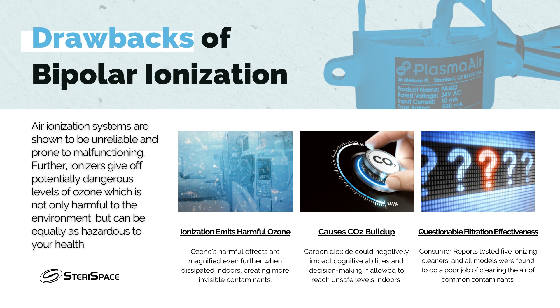There are other technologies available for treating indoor air, such as bipolar ionization, which cleans the air inside buildings using an electronic charge to create a plasma field filled with ions, robbing them of their life-sustaining hydrogen particles. Unfortunately, there are major drawbacks with bipolar ionization, such as hazardous environmental effects. Ionizers generate potentially dangerous levels of ozone, which could be harmful to us and our environment. The long-term CO2 buildup negatively impacts cognitive abilities. And the efficacy is questionable and certainly cannot make the claim of air sterilization.